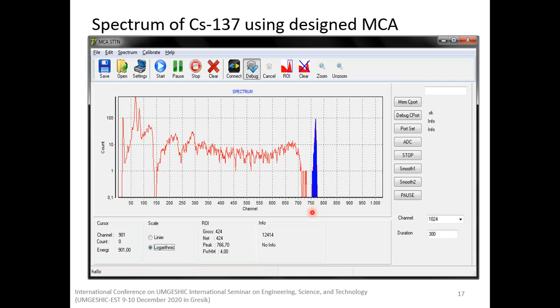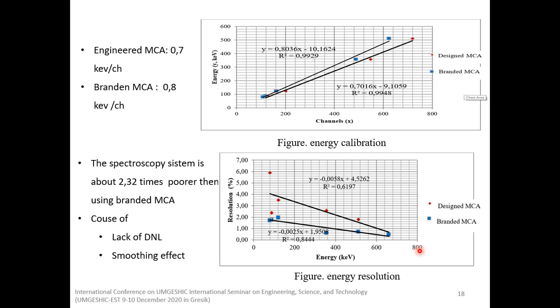Energy calibration: the figure above shows a comparison of energy calibration between the designed MCA and the branded MCA. I mean, the branded MCA is an MCA from the country of origin, so both MCAs are linear with 0.7 kiloelectron volt per channel and 0.8 kiloelectron volt per channel respectively. Below, it shows that the designed MCA energy resolution is 2.3 times poorer than the branded MCA because of the lack of DNL, which leads to poorer energy resolution.